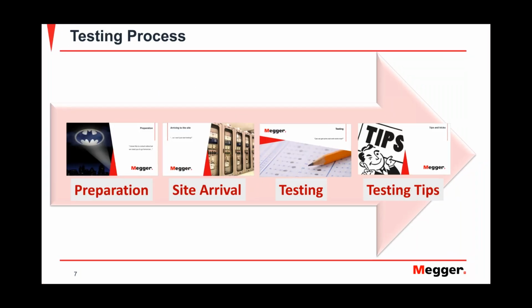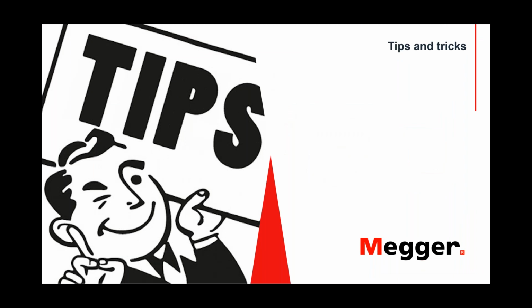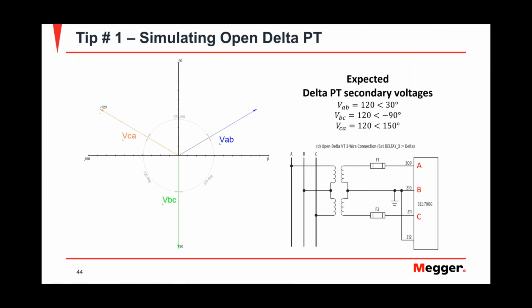Now I'm going to move really quick on some tips and tricks. I still get a lot of questions on how to test a relay that is being fed by an open delta. How do I simulate an open delta connection going into a relay? For this, I'm going to use an example from an SEL, and this is how Schweitzer wants you to wire, in this case, an SEL-700G. You have an open delta PT, and this is the expectation on the voltages. You have your voltage A and B, your line-to-line voltage, 30 degrees from what would be a line to neutral. Your B and C is minus 90, and your C and A is at 150.